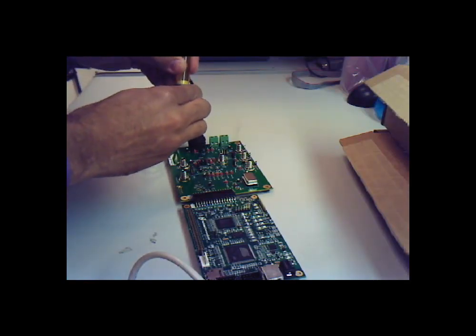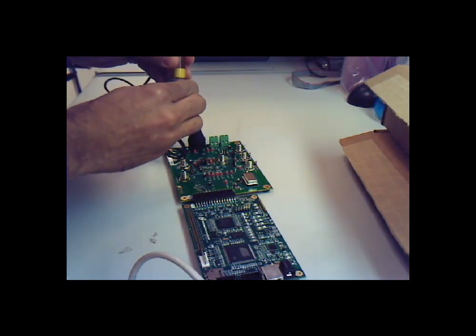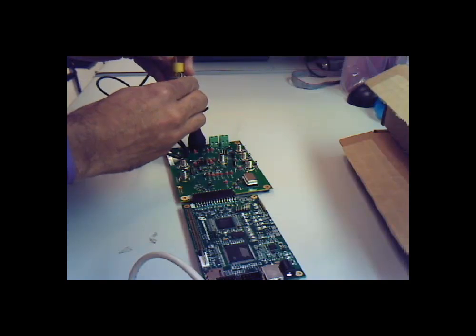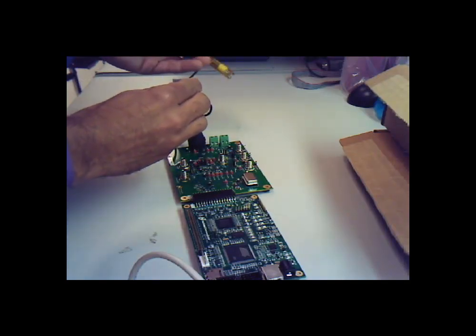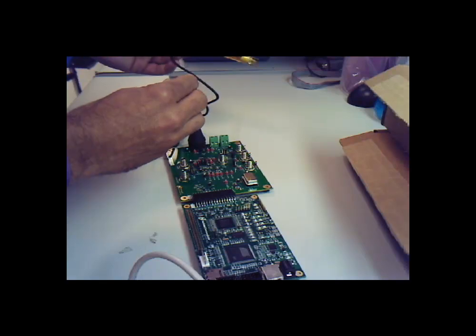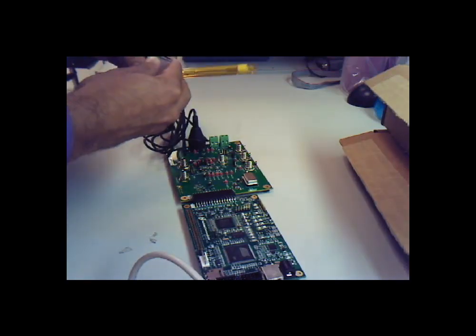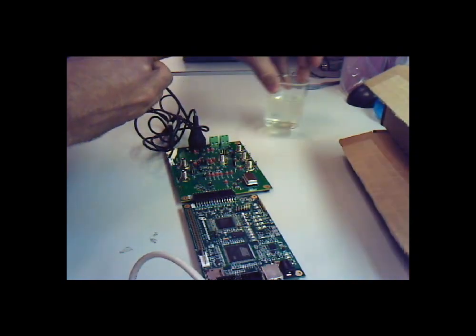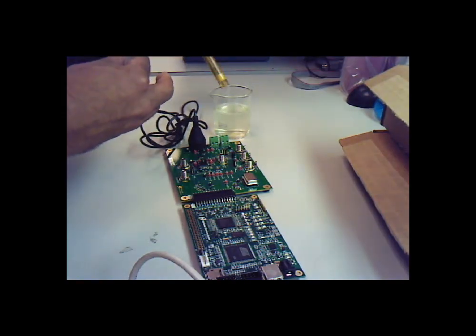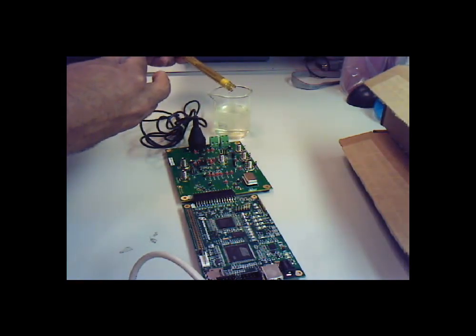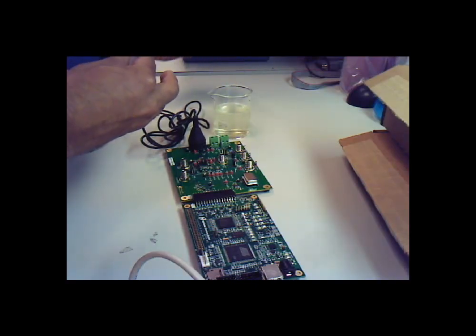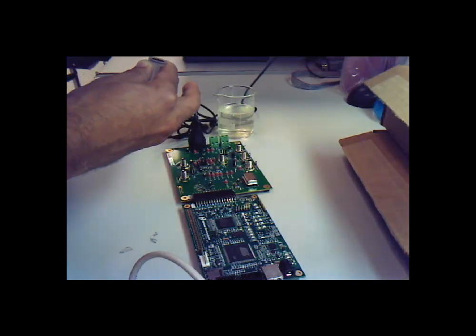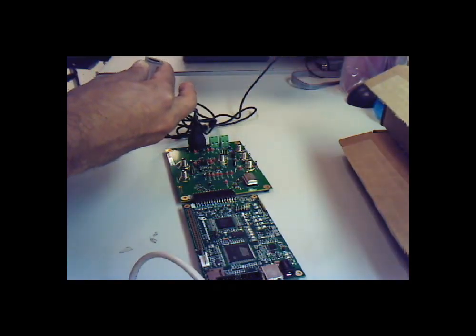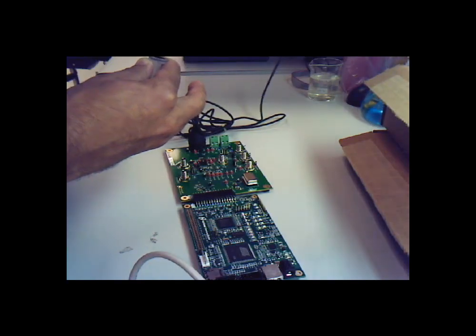You'll have a cap on the pH sensor, which basically contains a solution so the actual pH sensor won't degrade over time. We're going to rinse that solution in distilled water, and then put the pH probe into a known test solution, which has a pH of 10.